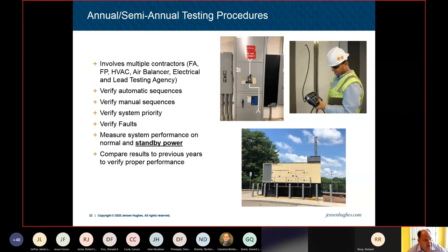Now, during that testing, we're not only verifying the automatic sequences, we're verifying the manual sequences, since the newer systems have smoke control panels, firefighter smoke control panels, whatever you want to call it.